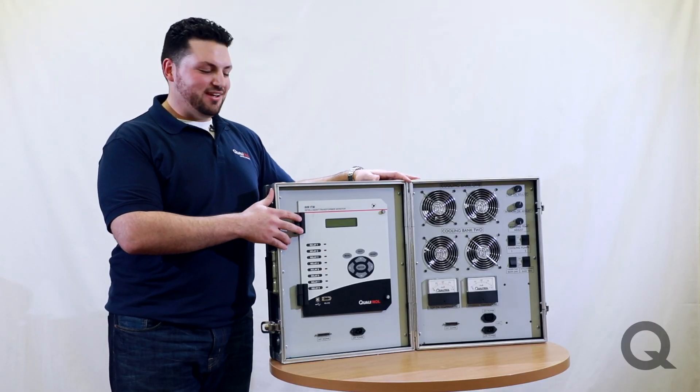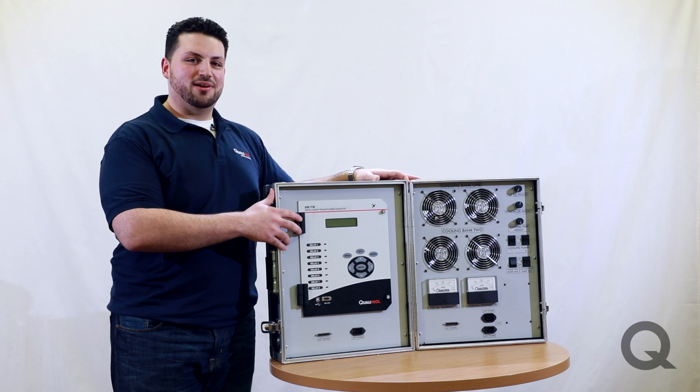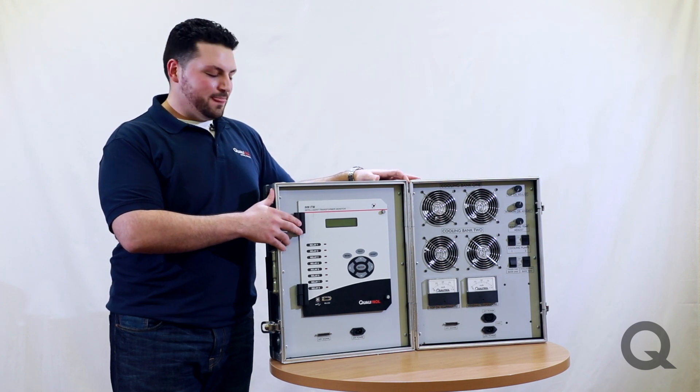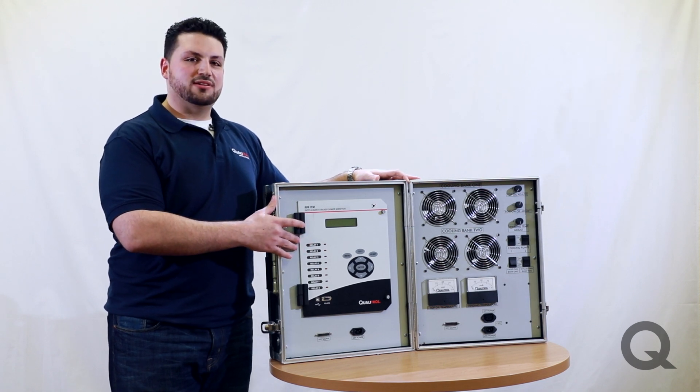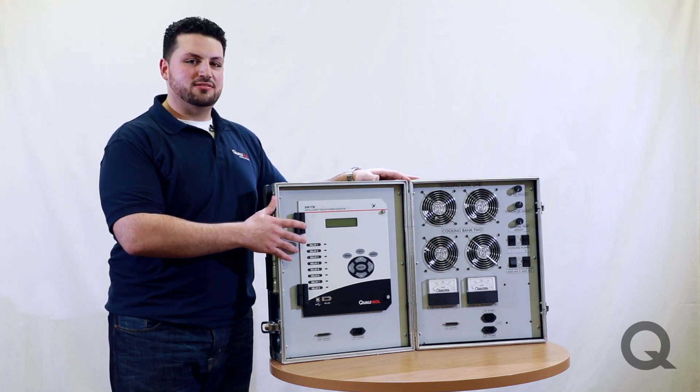With the 509 ITM you also have the option to do real-time direct winding monitoring using fiber optics. This is done with a hotspot module that will be located behind the ITM 509. Typically our customers like to monitor 8 to 16 fibers depending on the application.